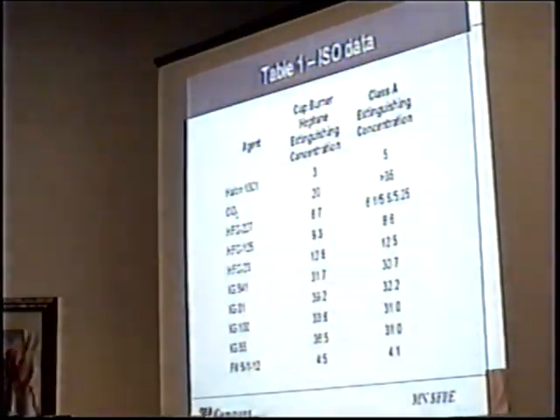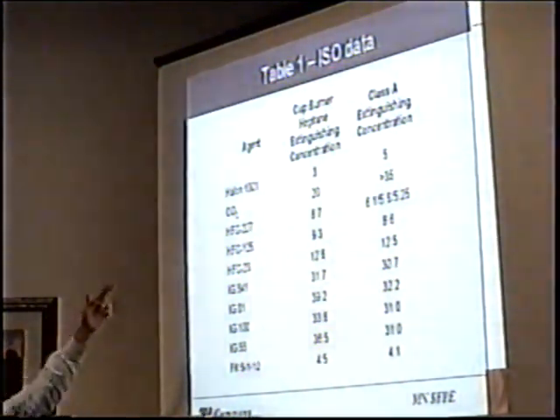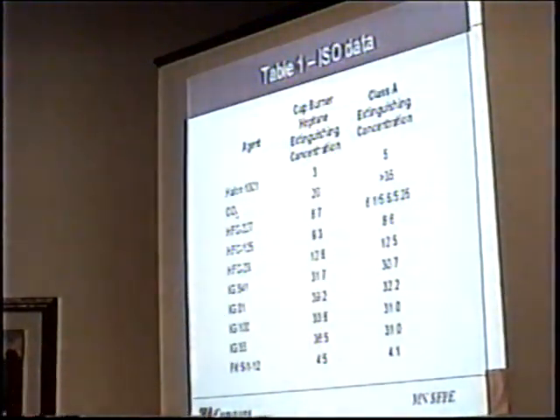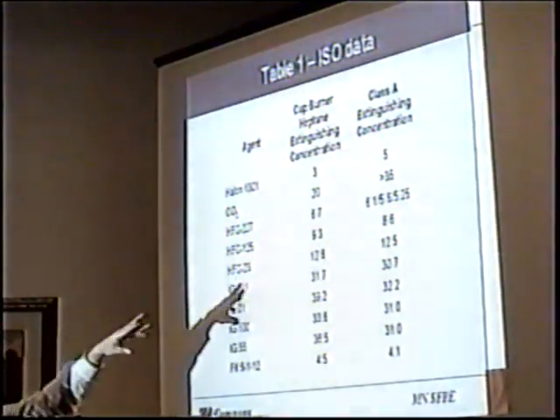One other thing here, we're looking at the safety factors, and here's a comparison of the various agents that are in the standards right now. You see the cup burner heptane extinguishing concentration for those agents, and the Class A extinguishing concentration for those same agents. Do you see something about those different agents that's different? Is that unusual? 227. Why is there 3?